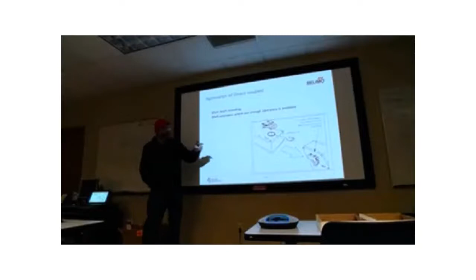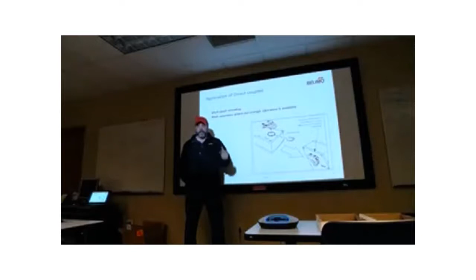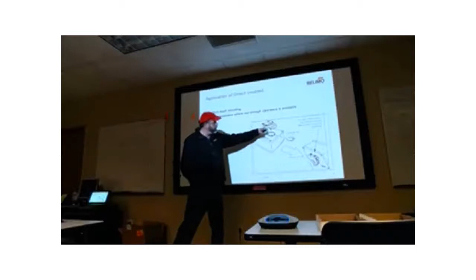I don't know if you've ever done this, but if the shaft coming out of the damper isn't long enough to get through the actuator, you can reverse it and put the clamp on the other side. It's got to have enough shaft for the clamp, but you can flip it and mount it on the other side. You'll need a nut driver or an impact wrench to get it done, but you can do it.